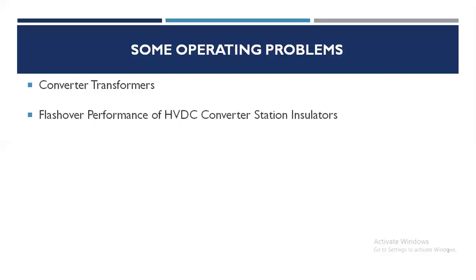Second problem is regarding the flashover performance of HVDC converter station insulators. Insulators such as valve bushings, capacitive voltage dividers and voltage transformers suffer external flashover caused by rain, fog, snow, and ice. At some converter stations, there were several flashovers at the beginning of their operation. The maximum flashover rate occurred between 1987 and 1989, involving about 20 flashovers per year. Most flashovers occurred in the valve bushings, followed by large diameter insulators. The valve bushing flashovers occurred mainly in the rain and at negative polarity.